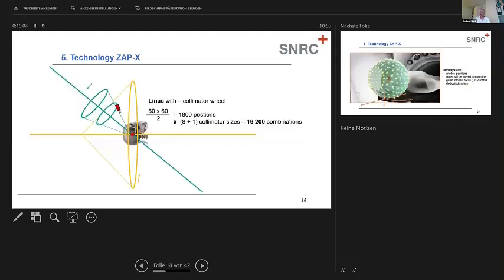If you look from a theoretical consideration at the potential positions, there are 16,000 combinations, because you have an inner sphere where you can stop every 6 degrees, leaving 60 positions. And you have this for both spheres. So it's 60 multiplied by 60 and divided by 2, because 2 positions kind of extinguish themselves. So it's 1,800 geometrical positions multiplied by 9 potential collimator positions, and that leaves you with 16,000 combinations, out of which you usually use no more than 200 to 300 beams.